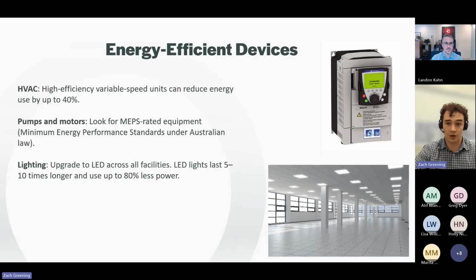VSDs also have a life cycle bonus for your equipment. The lower runtime and better control means fewer breakdowns and longer life for compressors and fans. Many base building systems still rely on fixed speed motors and legacy fans that run at full tilt regardless of demand. Under Australian law, new commercial motors and appliances will have to meet minimum energy performance standards, or MEPS. So upgrading to these MEPS compliant or high efficiency models can offer a 15 to 30% energy savings per unit. They have less noise, vibration, and heat generation, which means reduced operating temperatures and less cooling load.